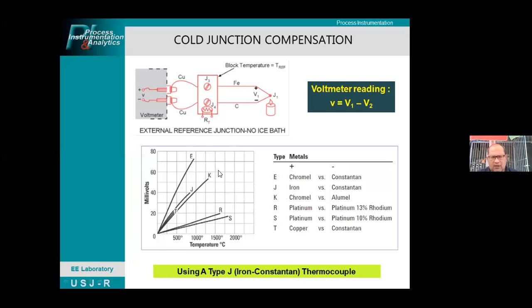In this graph, the highest reaction in terms of millivolts is this type E, the chromel versus constantan. As the temperature increases, the millivolts of this thermocouple also increase, with this particular type of metals. For the type J, you have iron and constantan. So it still depends on the type of metals being used and also on the application.